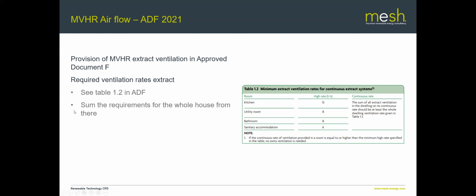So what you have to do is sum the requirements of the whole house from this table and check whether that exceeds what we've calculated for the supply, which is again that floor area times 0.3, or the minimum given in table 1.3. So whichever the higher of those two is what you end up using.